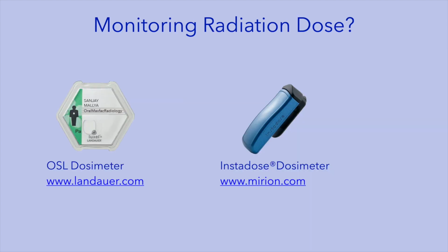To ensure that you and your staff consistently follow radiation safety precautions, you can monitor radiation dose using these radiation dosimeters. The two dosimeters depicted here monitor full body dosage. These monitoring devices are typically clipped onto the clothing on the front of the chest. The OSLD dosimeter, or optically stimulated luminescent dosimeter, is provided by a service and is typically returned on a monthly basis for dose monitoring.